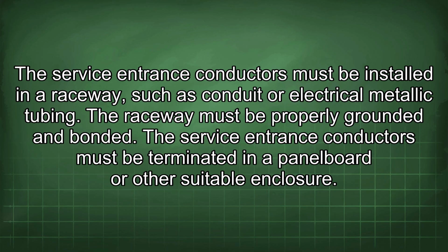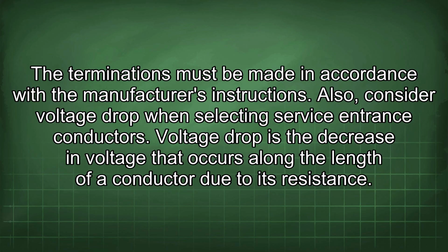The raceway must be properly grounded and bonded. The service entrance conductors must be terminated in a panel board or other suitable enclosure. The terminations must be made in accordance with the manufacturer's instructions. Also, consider voltage drop when selecting service entrance conductors.